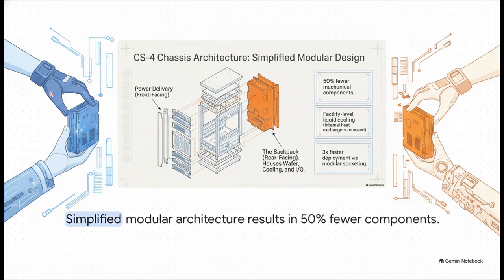Zooming out to the wider chassis architecture, the orange backpack simply slots into the rear of the rack frame, while the power delivery modules slot into the front. By totally removing the internal heat exchangers and relying entirely on facility-level liquid cooling, this design achieves 50% fewer mechanical components. That simplification heavily lowers manufacturing and assembly costs, which nicely offsets those much more expensive thermal requirements.